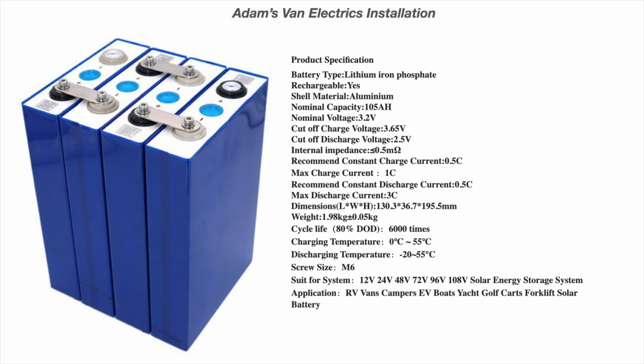So we start with the batteries. These are 105 amp an hour, 3.2 volts each cell. Combining in this configuration will give you a 12.8 volt battery at 105 amps. They will do 80% depth of discharge and they'll do 6,000 cycles, which is fantastic.